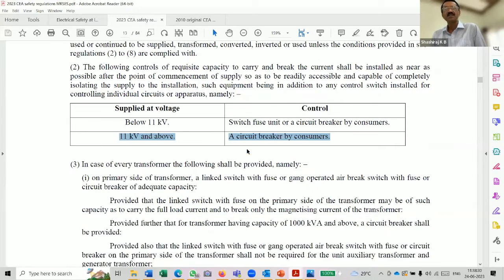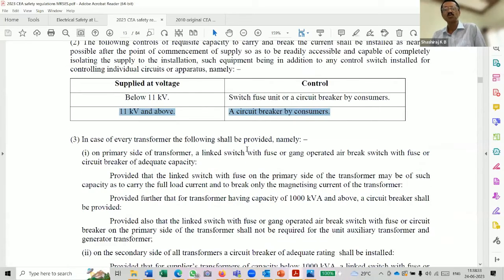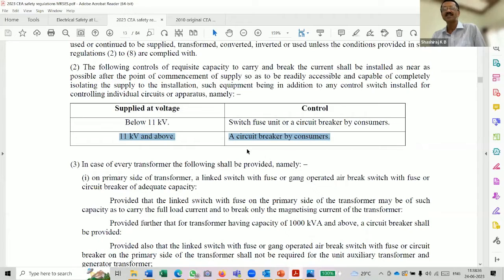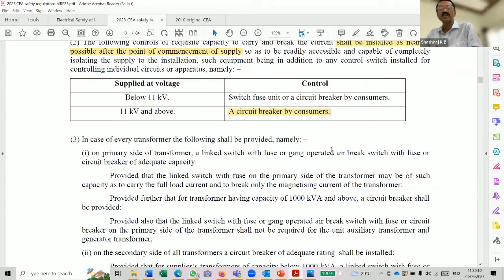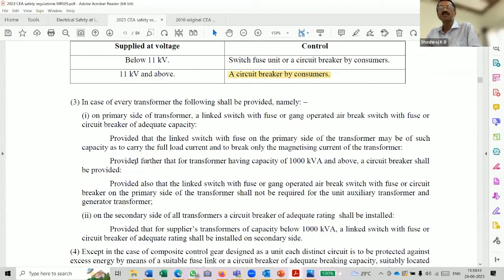and then only is it applicable to most of the installation. Whereas very clearly 37.2 states that it is at the point of commencement of supply, and it also says that it is to be provided by the consumer. Obviously, it goes without telling that it is applicable only to consumers, and regardless of load, based on voltage only, the requirement of primary protection is to be provided. Obviously, this 37.2 does not apply to DISCOMs, but it does apply to DISCOMs when you come to 37.3, where it speaks of only a transformer. We have to read it very carefully.